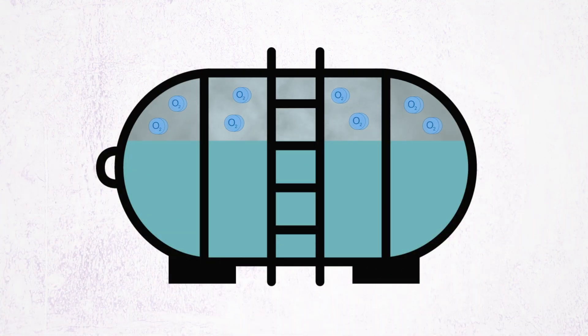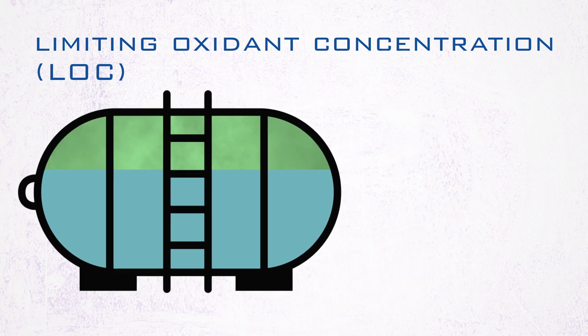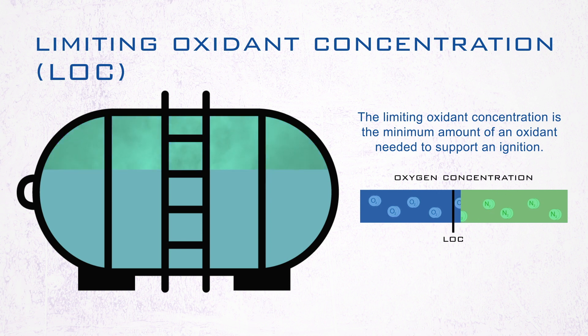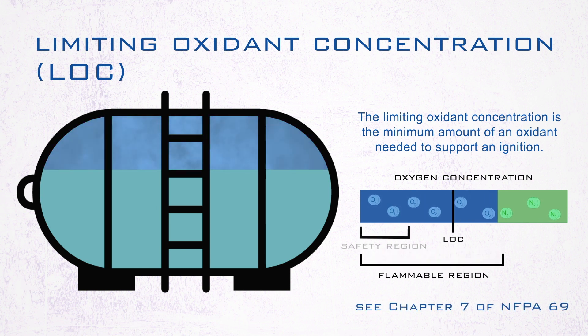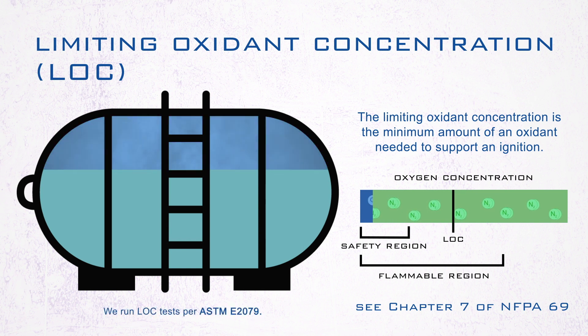If operating outside of the flammable region is not possible, the oxidizer can be reduced to create an inert environment. Limiting oxidant concentration (LOC) is the minimum amount of an oxidant needed to support an ignition. Knowing the LOC helps determine proper inerting and purging procedures to maintain safety while remaining inside the flammable region. Chapter 7 of NFPA 69 advises the permissible safety margin necessary when operating below the LOC.